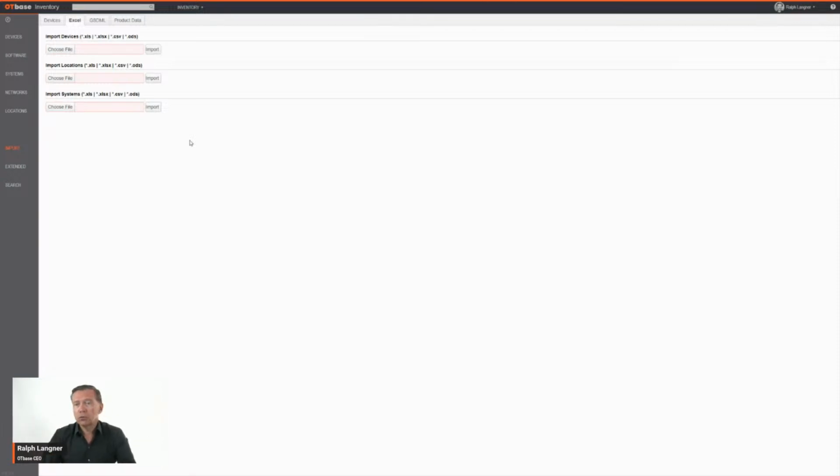And then the workaround is you take your DCS engineering application, or some DCS vendors also have a specific asset inventory application. Unfortunately, it lacks a lot of detail, it's not really user friendly, and it's certainly limited to the specific DCS of that vendor. But those applications often can export data, usually to an Excel file, and then you can import it here, so that you also get your DCS devices with their firmware versions, etc., in your global OT asset inventory that you maintain in OTbase.